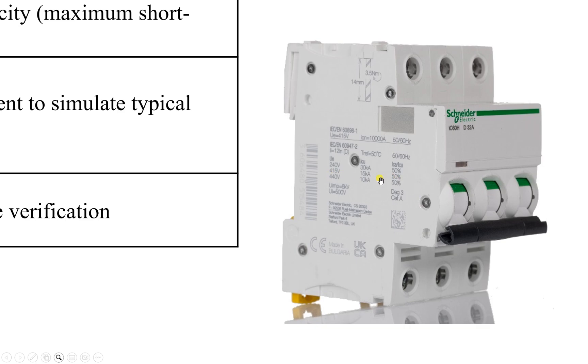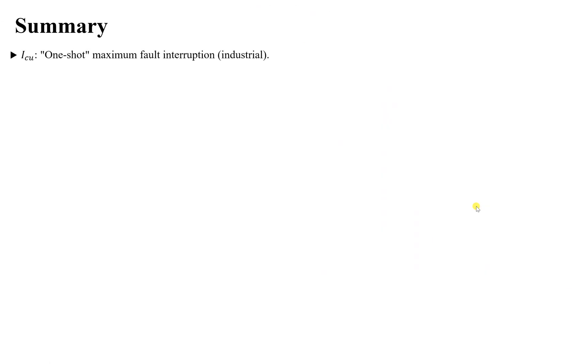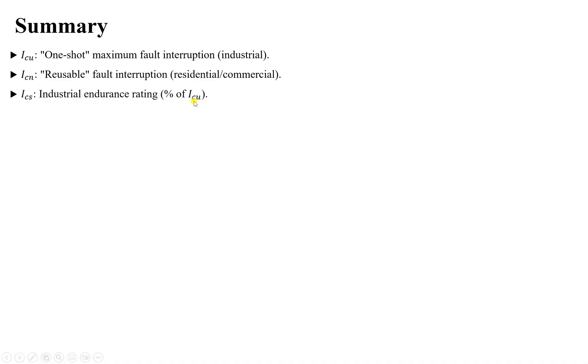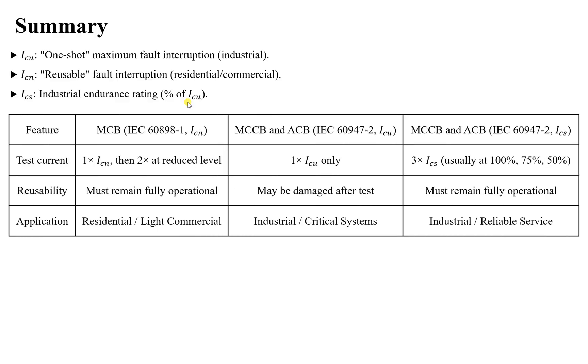To summarize: there are two IEC parts — IEC 60898-1 for household applications which defines ICN, and IEC 60947-2 for industrial applications which defines ICU and ICS. ICU is a one-shot maximum fault interruption for industrial use — the breaker must withstand it once. ICN means the breaker must interrupt the rated fault current several times, used for residential and commercial. ICS is a percentage of ICU indicating how many times the breaker can withstand faults repeatedly.